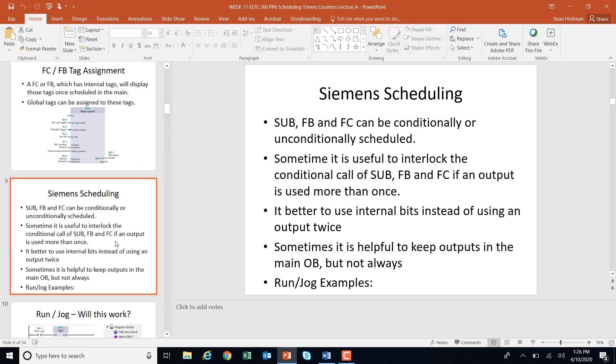These can be scheduled conditionally or unconditionally. Sometimes it's useful to interlock the conditional call if an output is used more than once. You really don't want to use an output more than once — that would be a very unique situation. It's better to use internal bits in an OR configuration than to use an output twice, so it's easy to troubleshoot. Sometimes it's helpful to keep outputs in the main OB, as we've done in some run/jog examples.